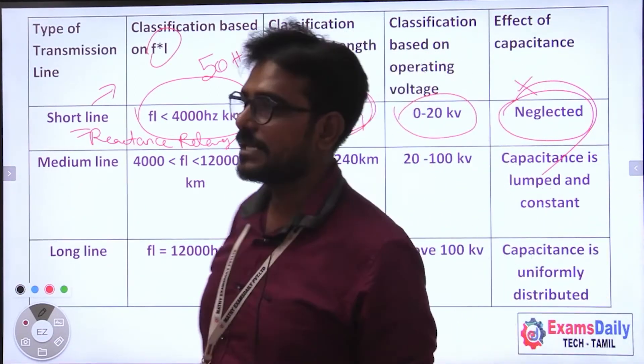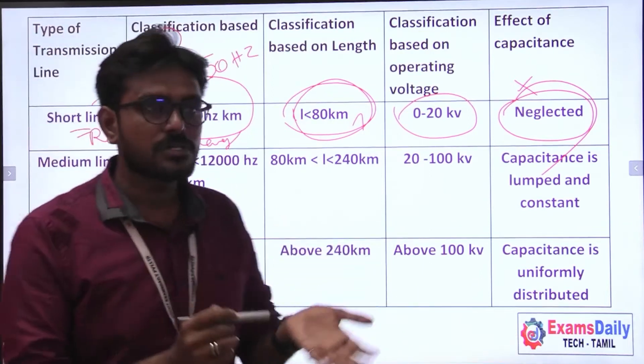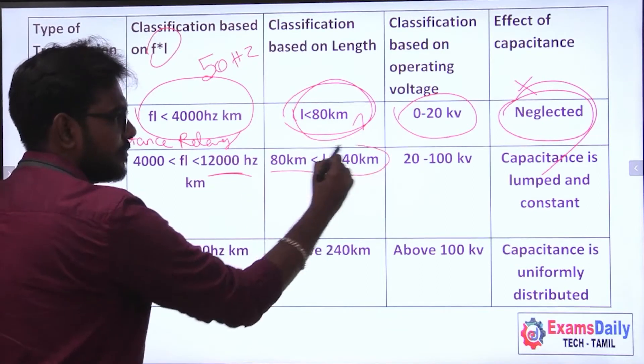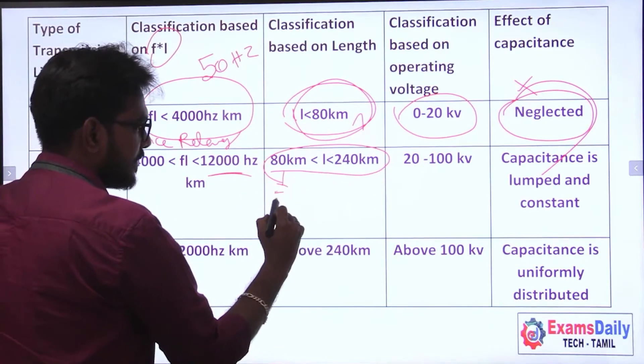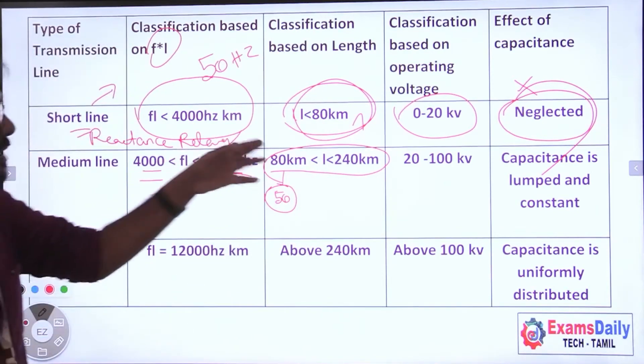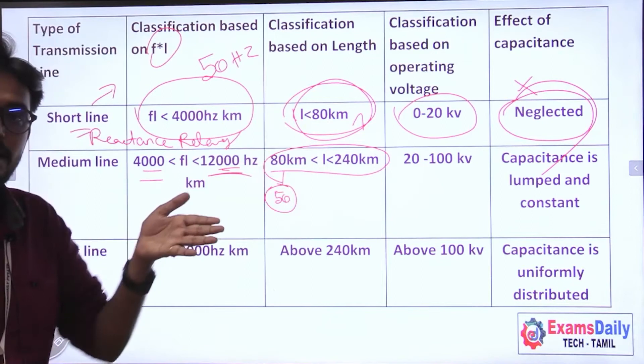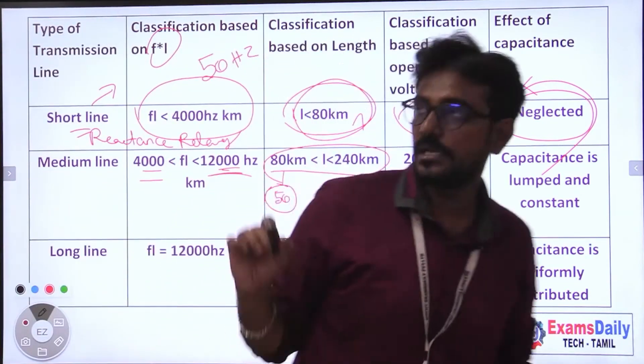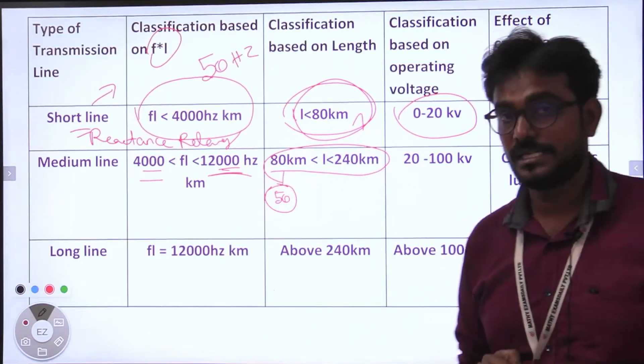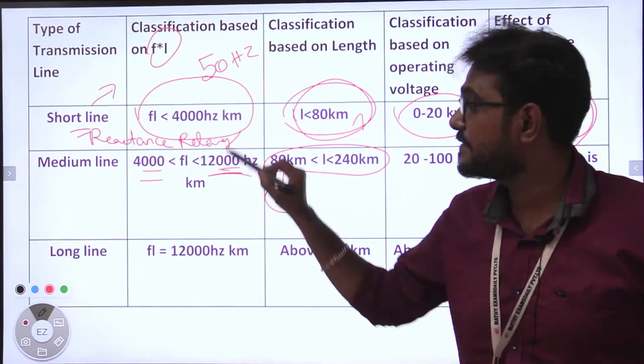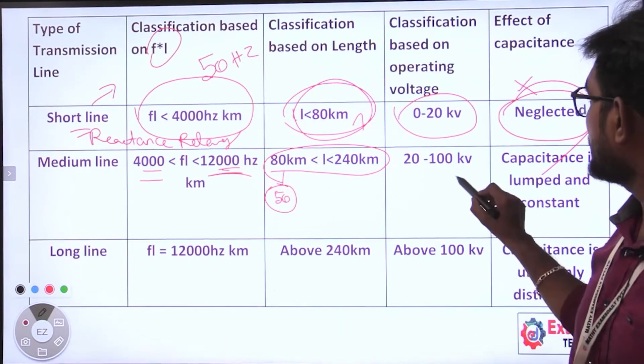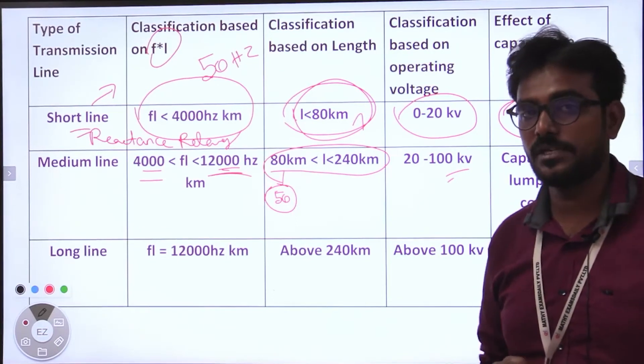Next is medium transmission line. For medium transmission, the frequency-length product is 4000 to 12,000. If you look at the km range, with frequency 50 Hz, it works out to 80 km to 240 km. The operating voltage for medium transmission line is 20 to 100 kV.